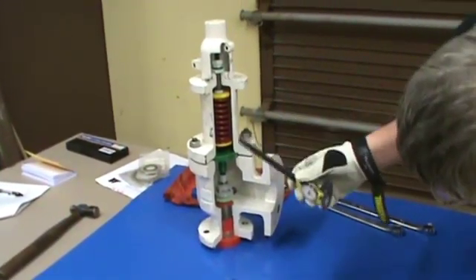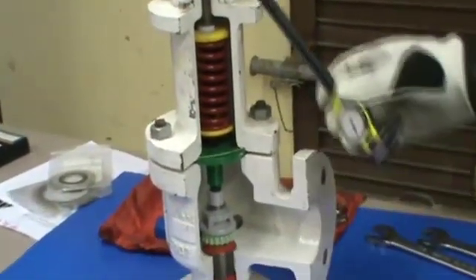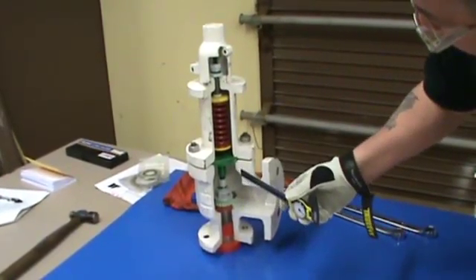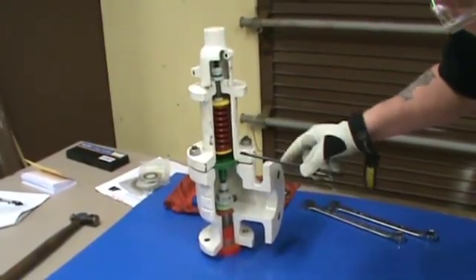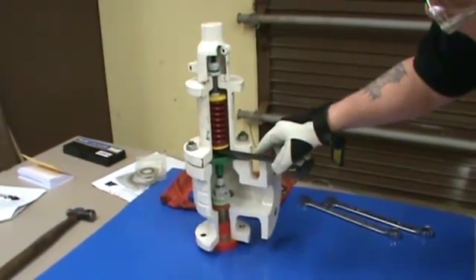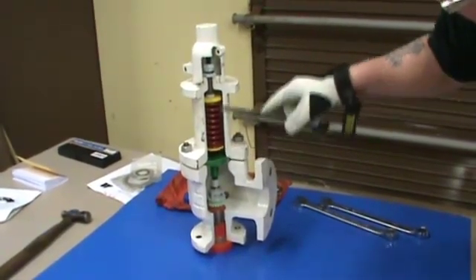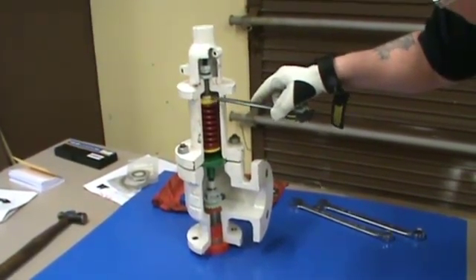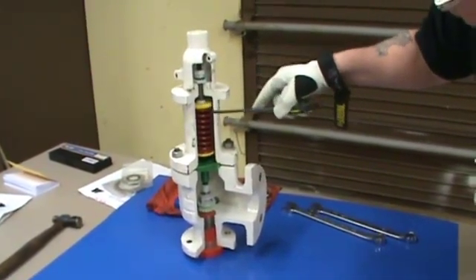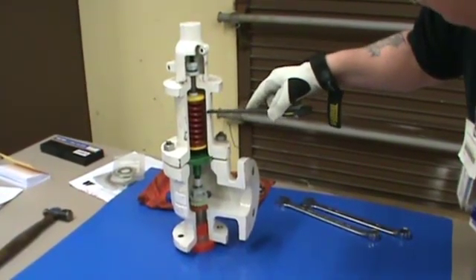I did not talk about it because it's very difficult to see, but you have your spindle, and in a normal valve that would be the stem, but in a relief valve it's called a spindle. Some of the main things to realize about the spindle is there is a bearing surface on the spindle which matches up with the lower spring washer. The top washer has a bearing surface which matches up with the bearing surface of the compression screw. It is a good practice to always grease those in to know that you have good contact.